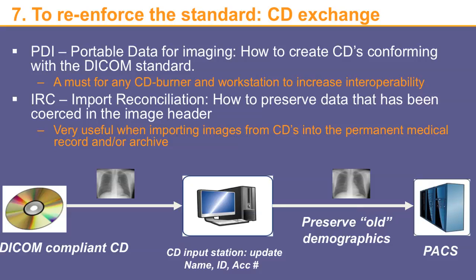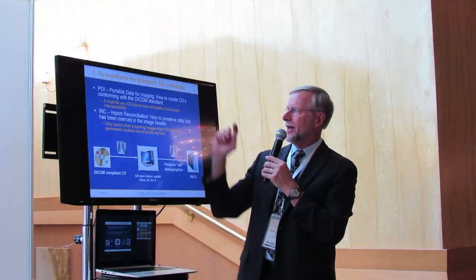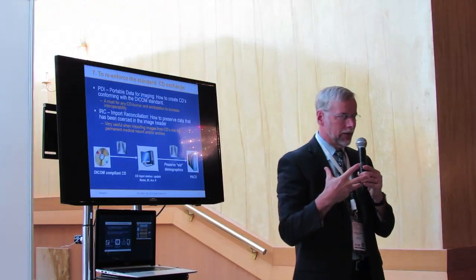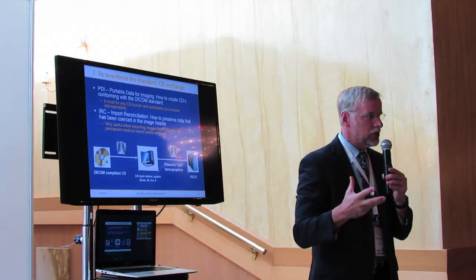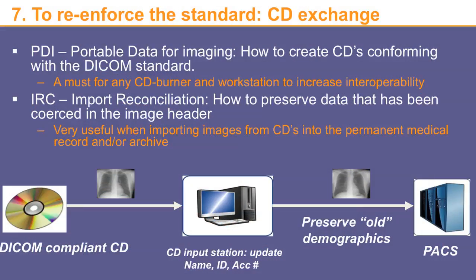I would definitely never purchase any CD burner or workstation that does not support the PDI profile. That's not really new or additional information in the IHE standard, but it's basically just to reinforce what the standard already says. Another related profile is the IRC, Import Reconciliation Profile, and that allows images that are imported to be reconciled with information about the patient that is either already available in the information system or will be created there.